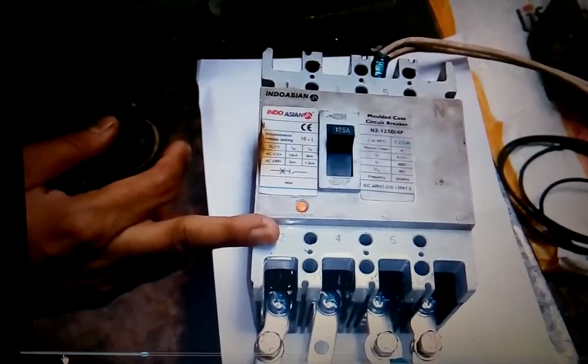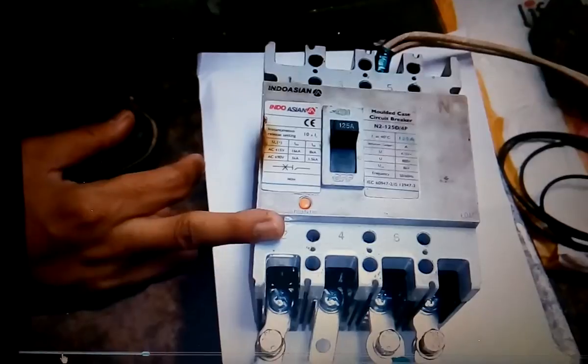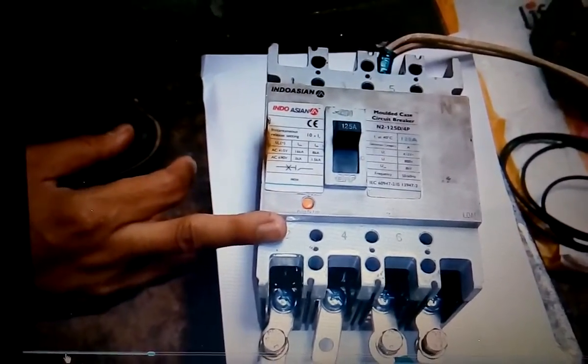So here for 125 ampere MCCB, we are planning to inject 350 ampere current through MCCB as one of the pole.